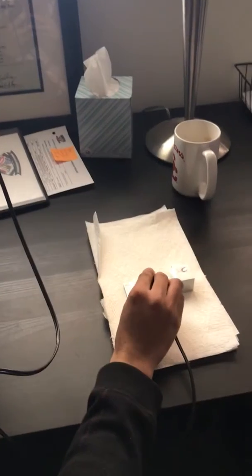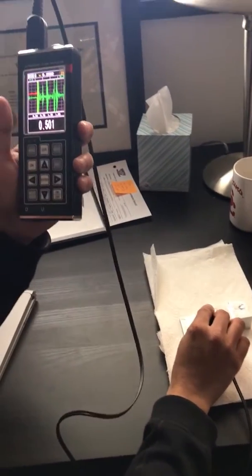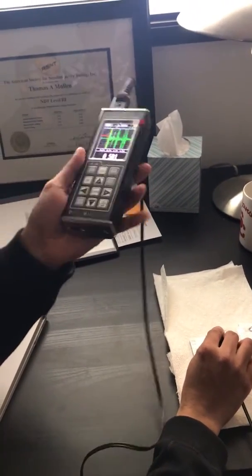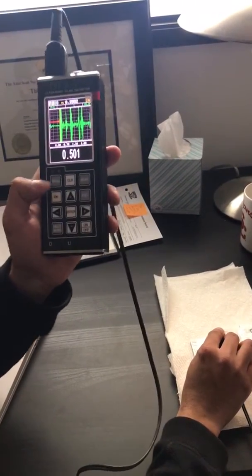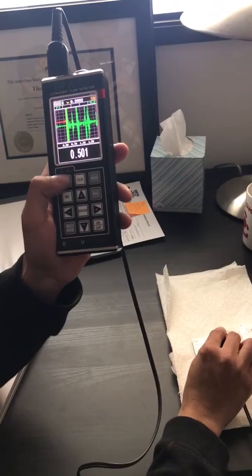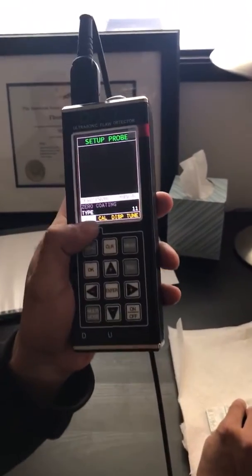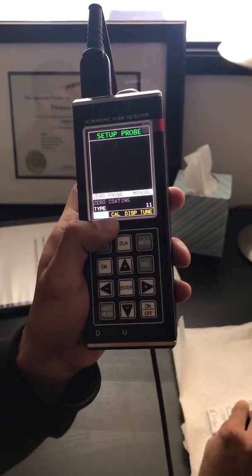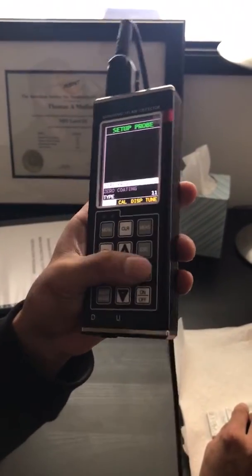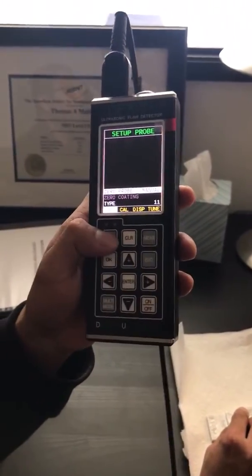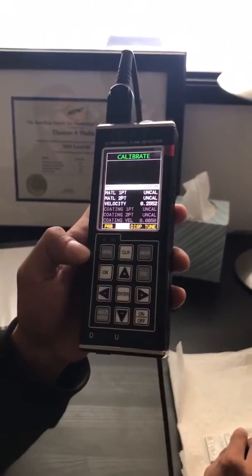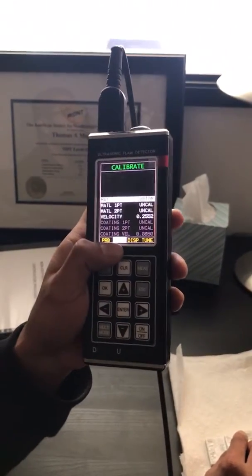You want to put it on thickness one. So I go back on menu, you see the second option is cal, so I'm gonna move on calibration. So I hit menu again which brings me on calibration first point.